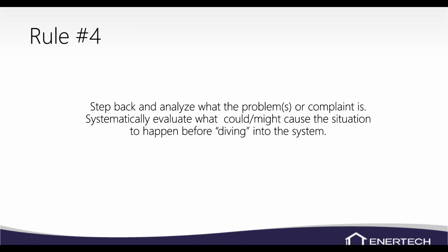Step back and analyze what the problem or complaint is, and then systematically evaluate what might cause the situation before just diving in. Again, analyze the situation. If you've got a low pressure lockout, I don't want you to immediately put your refrigerant gauges on the system. We'll go ahead and check our flow first because it could have a flow problem. And if we don't have to put our refrigerant gauges on there, we don't want to. Again, it's a sealed system, so we want to make sure that we're not pulling refrigerant out every time we put our gauges on it.